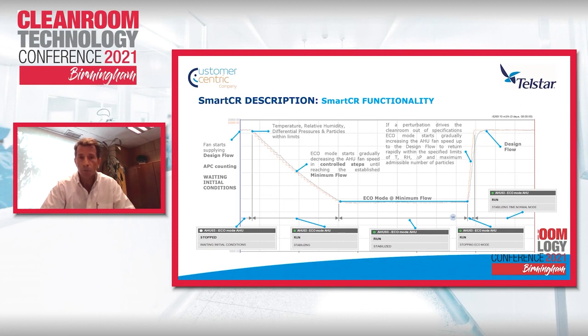We may have pre-calculated this minimum flow, but at the end of the day, we will reach it after practical trials of the installation itself. And then we will have another parameter, which is the ramp up. Whenever a perturbation happens in the room, particles, temperature, or whatever, we will react immediately to set the whole system again in the design flow. What we discovered is that the stability of pressures, temperature and humidity was easier to achieve when we were increasing the flow compared to when we are reducing it. So this is why the ramp to reach the minimum flow is longer, and the ramp up to recover the conventional flow is quicker. Also, we need to be quicker.